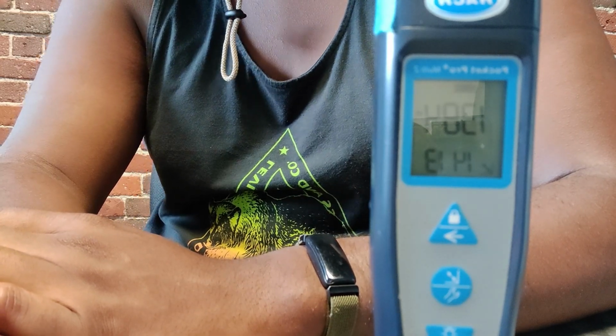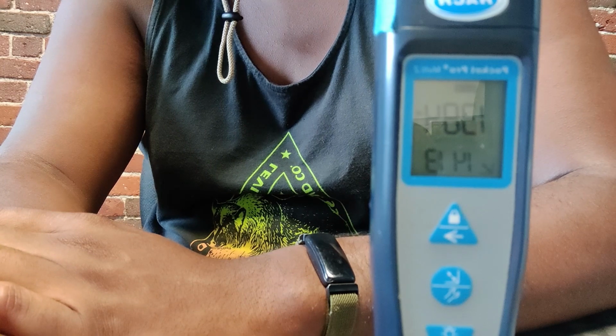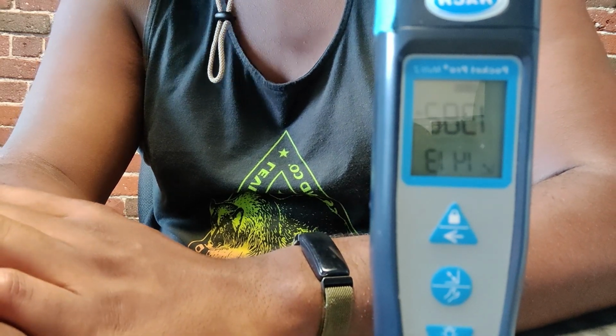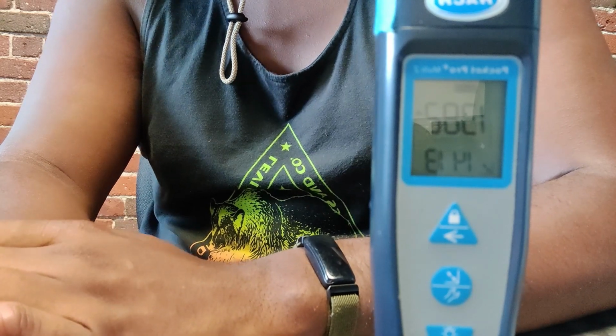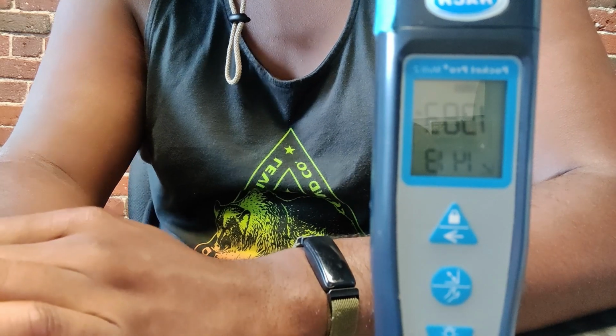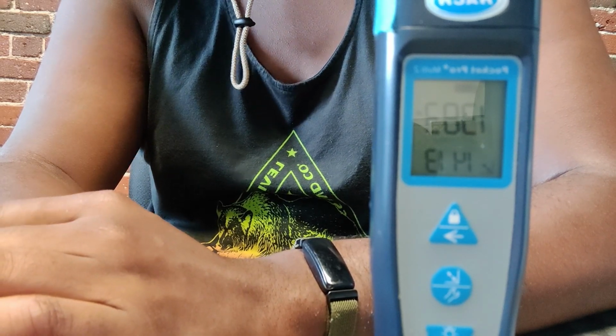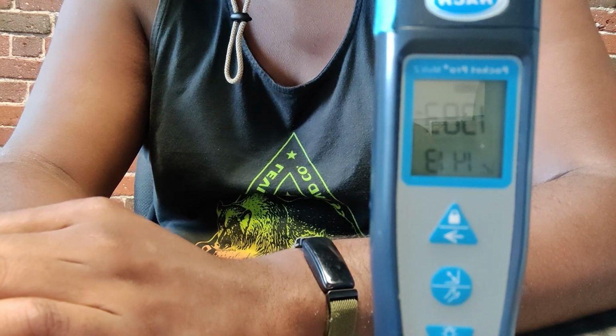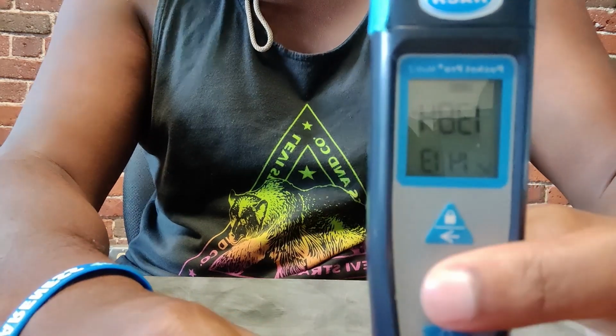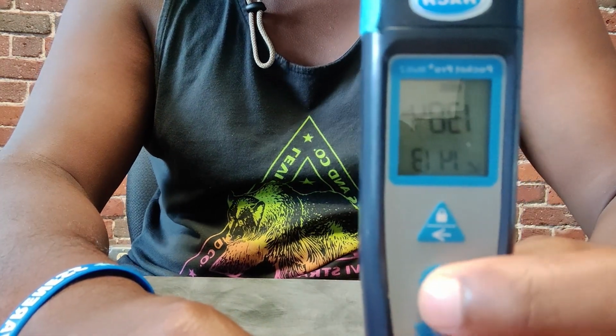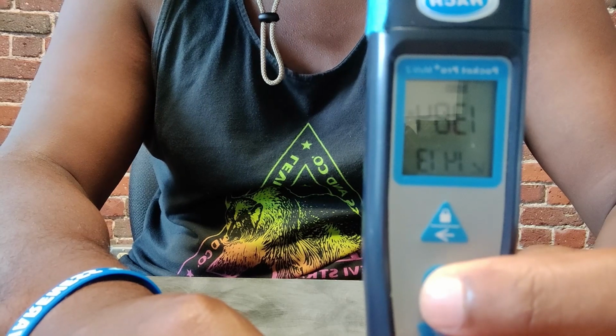Write down whatever number you see in the reading before calib box on your data sheet, remembering the unit. Where pH doesn't have a unit at all, conductivity has units that can change, called siemens. During calibration, it should be microsiemens. It will be to the right of the number on the top row with a fancy looking U with an uppercase S next to it. That's a microsiemen. The number will flash 3 times, confirming that the Hach has accepted the reading.